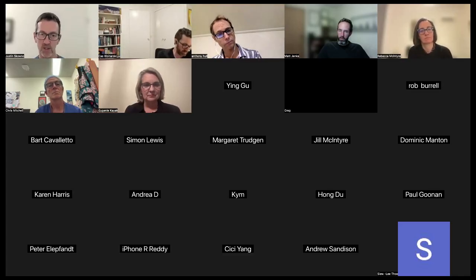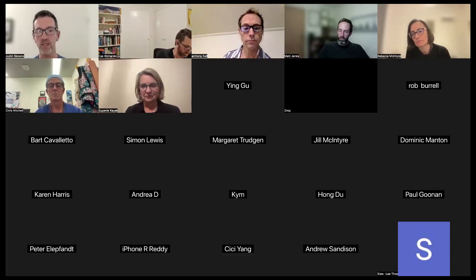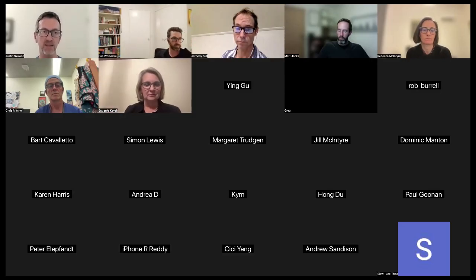Kath Asher's got a question in the chat there, just asking about safe disabling of the wall unit when decommissioning. And we are literally working on that solution. And I'd be interested in Matt, Chris's experience here. We've seen the caps that go on, and obviously the system gets depressurized. But what about just cutting the entire thing out and leaving a blank space on the wall? What approaches have been used when you've got a decommissioned system to make it look nice and sweet?